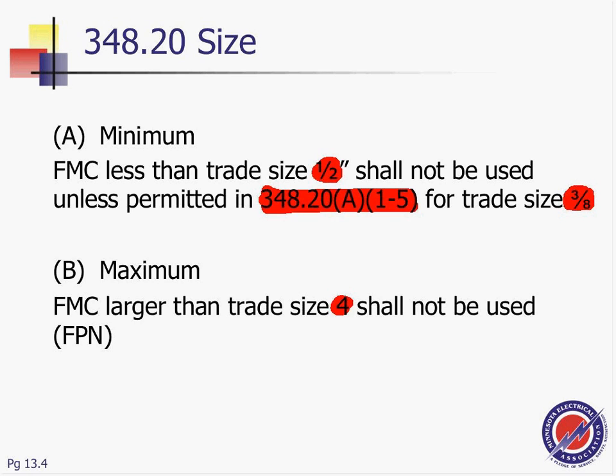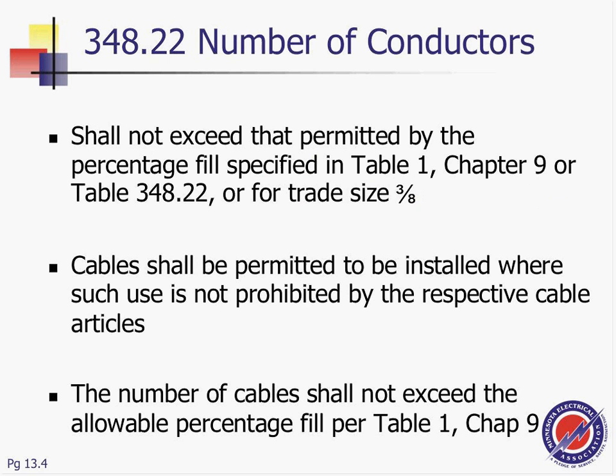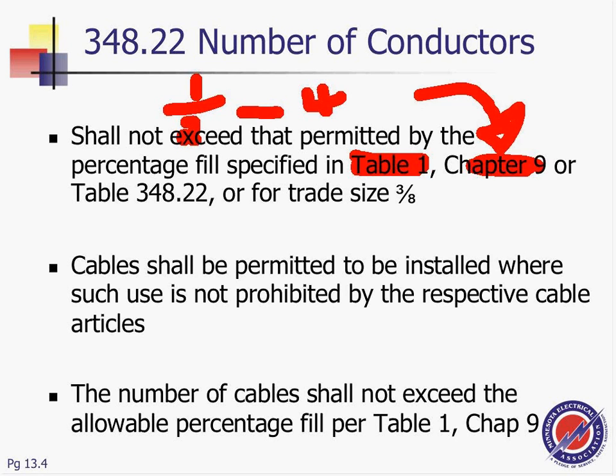Okay, it's a conduit not to sneeze at. It can get you all the way up to 4 inch. That's nothing to sneeze at, I guess, up to 4 inch. Now, conductors, guys, we're going to go to Table 1, Chapter 9. If the conduit is 1/2 all the way to 4, you're going to go basically to Chapter 9, Table 1.